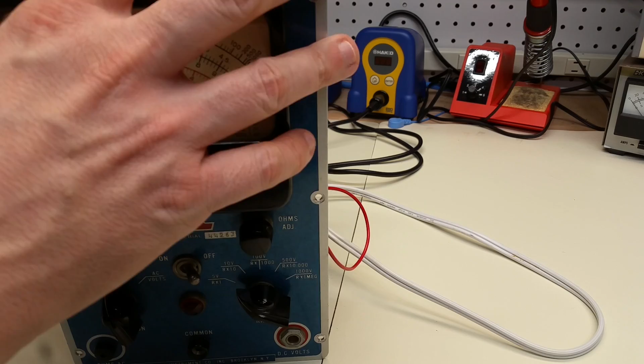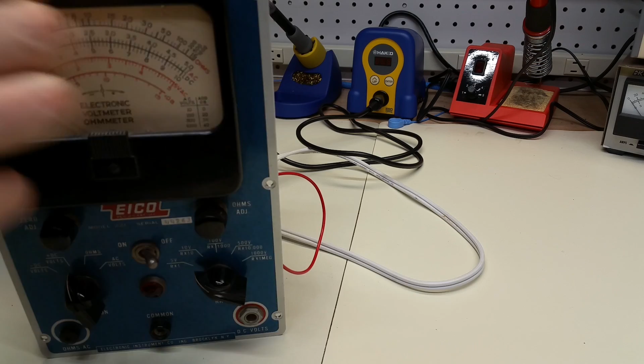All right, let's set this up here and bring it over. The way that this is calibrated is with a series of adjustments to these four potentiometers here, and so this has to be out of the case in order to calibrate it. So let me set this up here. All right, I've centered this so that we can see what's going on, and we're going to proceed to calibrate this EICO 221 vacuum tube voltmeter.